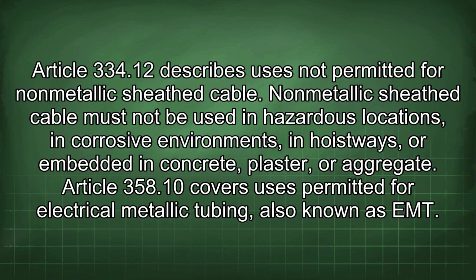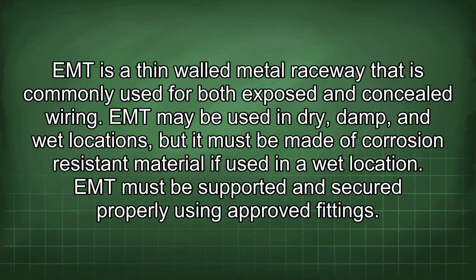Article 334.12 describes uses not permitted for non-metallic sheath cable. Non-metallic sheath cable must not be used in hazardous locations, in corrosive environments, in hoistways, or embedded in concrete, plaster, or aggregate. Article 358.10 covers uses permitted for electrical metallic tubing, also known as EMT. EMT is a thin-walled metal raceway that is commonly used for both exposed and concealed wiring.